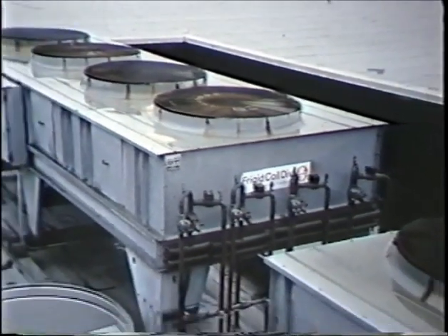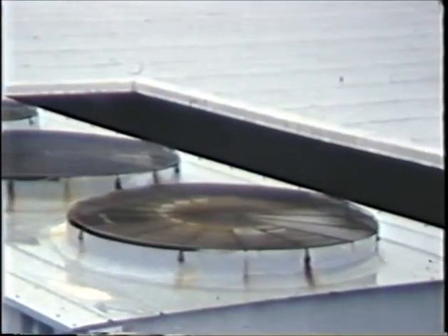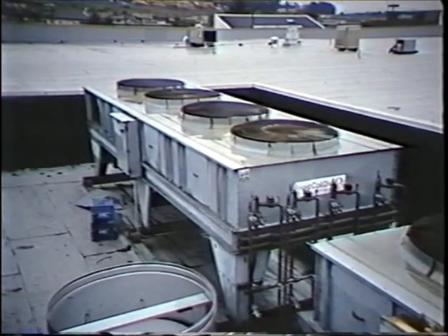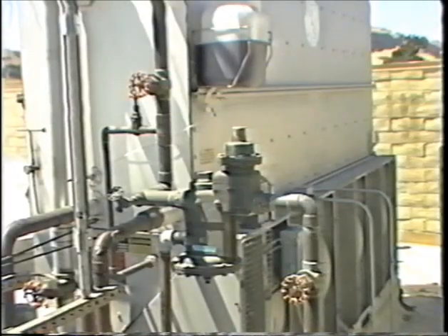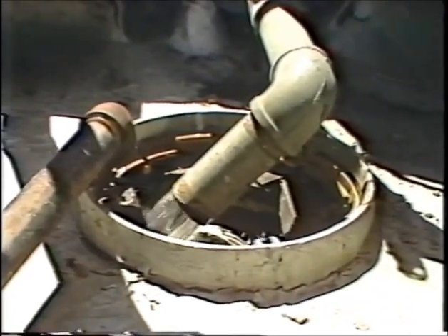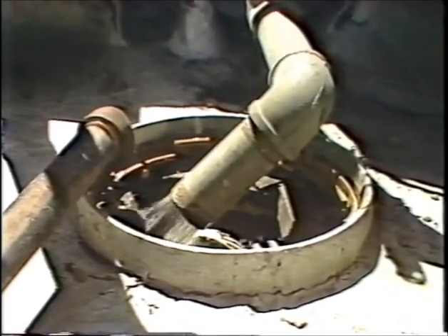Air-cooled condensers must be periodically inspected and cleaned. Remove any debris around the condenser or trapped underneath — even a slightly dirty condenser can add significantly to the compressor's electrical consumption. A clogged condenser will force a compressor to operate beyond its limits and shorten its life. For those stores with water-cooled condensers, check the drain line for the amount of water bleed-off. If the condenser is draining a significant amount of water, notify the store manager or call for service.